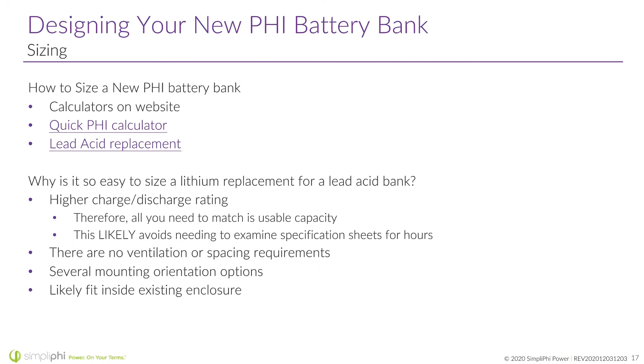As far as equipment compatibility, since you're replacing your batteries, make sure your charge controller or inverter have the right programming capabilities. So you want a low battery cutout of 48 volts. That's the minimum your battery should ever discharge to for 5 batteries. And on the high end, you want to program your absorb charge to end at 56 volts.